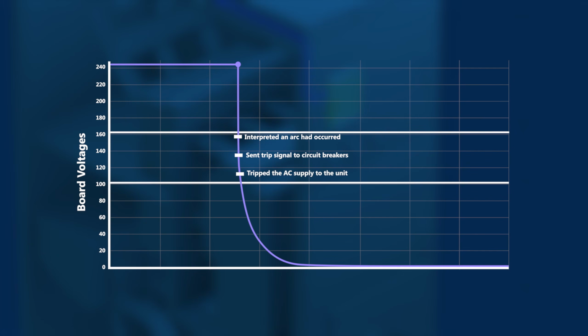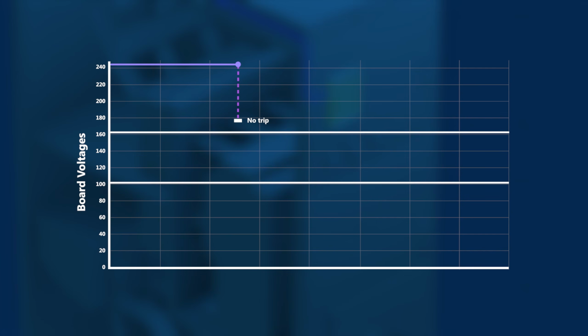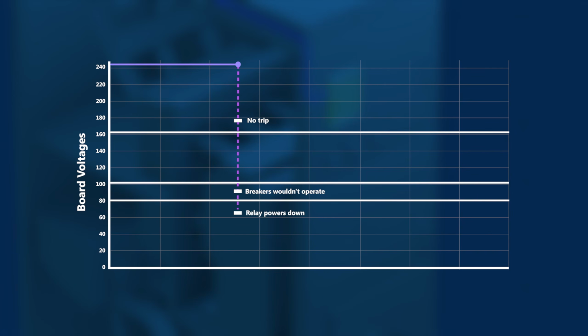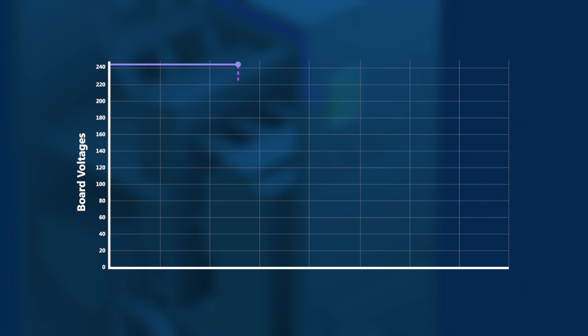decayed below 101 volts. If the voltage had remained above 164 volts, the protection relay would not have determined that an arc had occurred, and it would never have initiated a trip of the AC. If it had collapsed below 101 volts, there would not have been sufficient voltage for the breakers to operate. If it had collapsed below 80 volts, the protection relay would have powered down before it could initiate the trip.